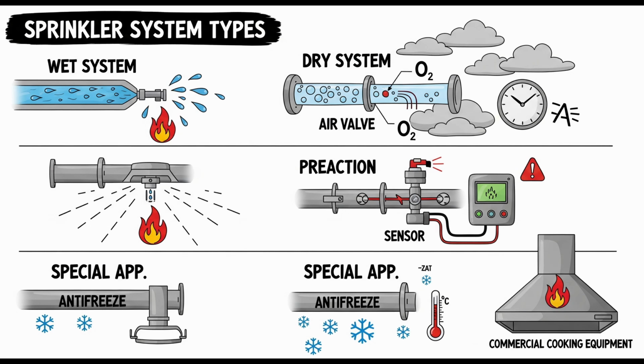Makes perfect sense. And the air or nitrogen supply used for systems in refrigerated spaces has special rules aimed at providing the driest possible air or gas into those cold pipes, going beyond standard dry pipe requirements. What are the options for this super dry air? The permitted options are: 1. Drawing the intake air for the compressor directly from the room of the lowest temperature within the facility, because colder air inherently holds less moisture. Yeah. 2. Using a specifically listed air compressor that comes as a packaged unit with an integrated air dryer designed for this application. 3. Using compressed nitrogen gas supplied from cylinders instead of compressed air; nitrogen is inherently very dry. So the engineering priority is crystal clear: introduce as little water vapor into the cold pipes as humanly possible right from the start. Precisely. Minimize the moisture source.